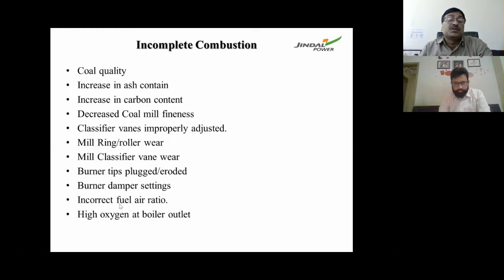Burner damper settings are very important. SADC should be checked regularly, and data should be maintained. Incorrect fuel air ratio can also occur. We have to closely monitor the oxygen percentage. Sometimes, due to various air ingress, the oxygen percentage can increase.